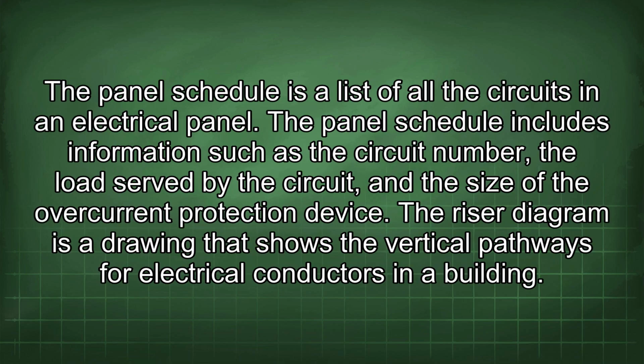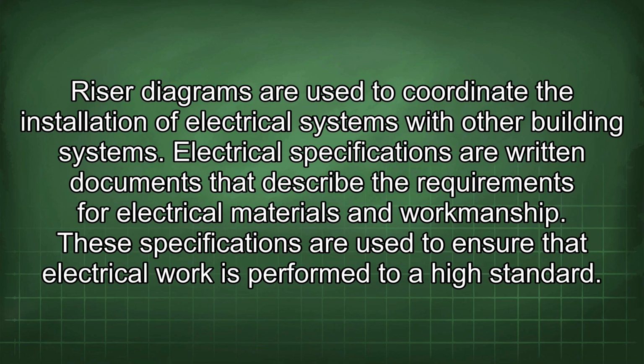The panel schedule is a list of all the circuits in an electrical panel. The panel schedule includes information such as the circuit number, the load served by the circuit, and the size of the overcurrent protection device. The riser diagram is a drawing that shows the vertical pathways for electrical conductors in a building. Riser diagrams are used to coordinate the installation of electrical systems with other building systems. The electrical specifications are written documents that describe the requirements for electrical materials and workmanship.